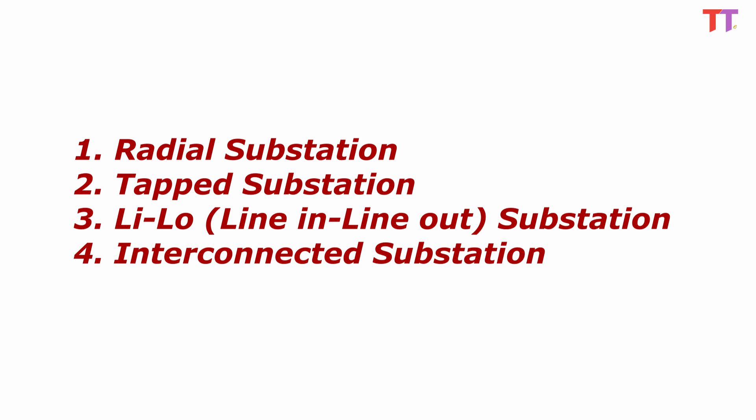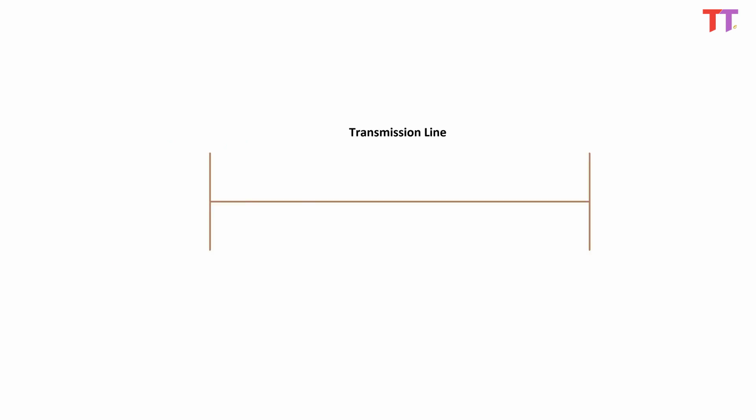Before starting with interconnection layouts, let's understand that every transmission line has at least two circuit breakers installed at the ends of the line. Also there are line and bus isolators on both sides of the circuit breaker. Hence in case of a fault on the transmission line, circuit breakers at both ends of the line trip, isolating the fault completely.